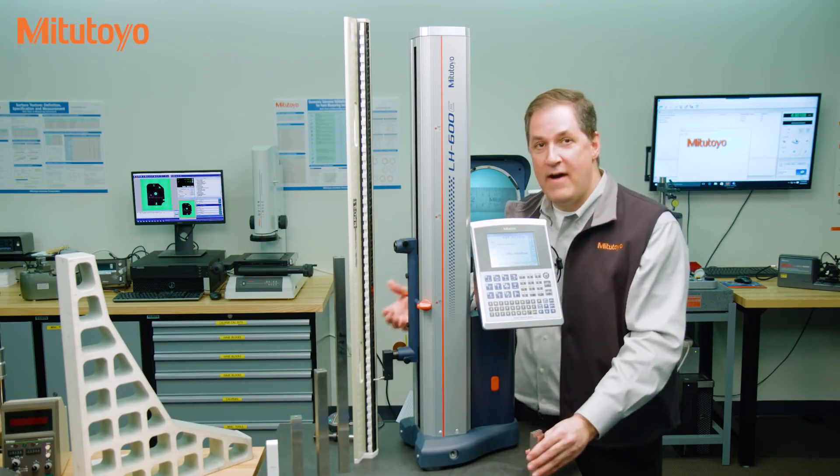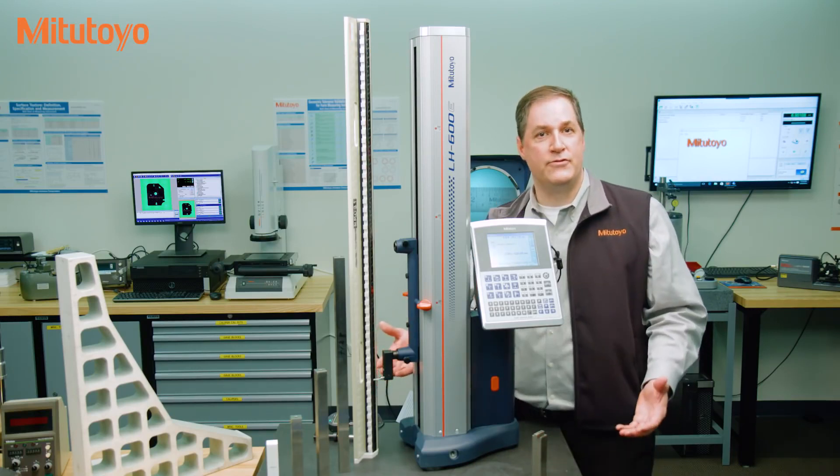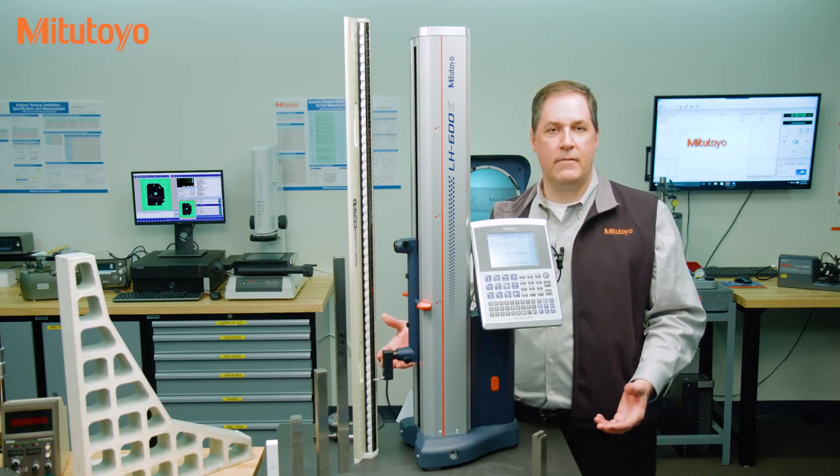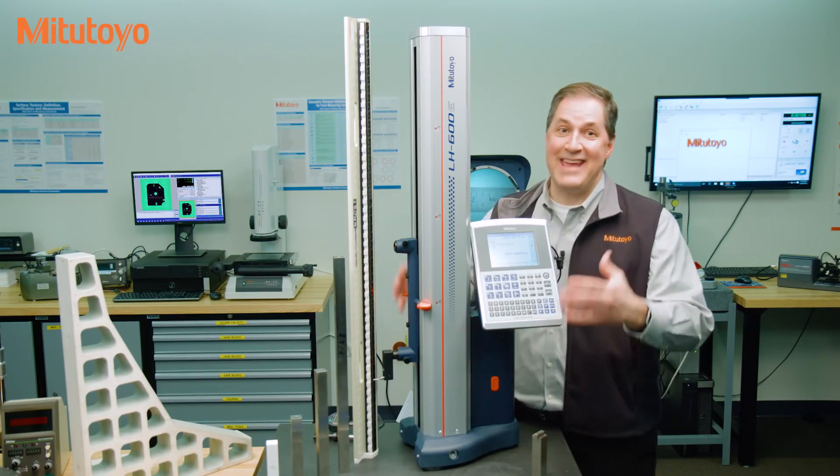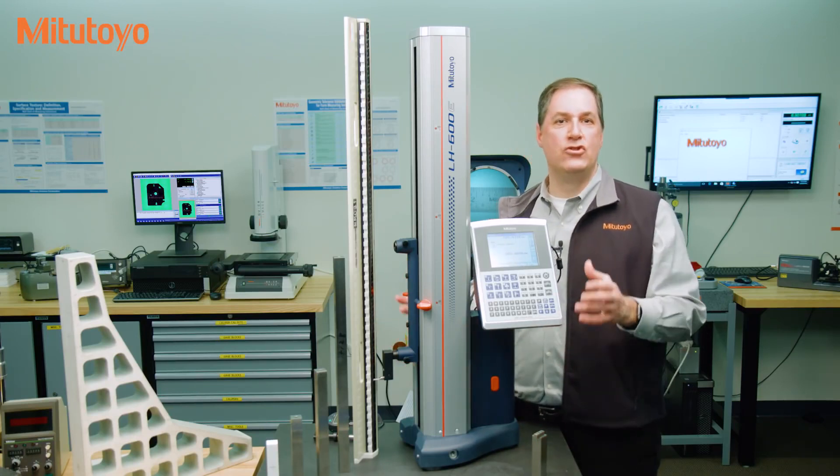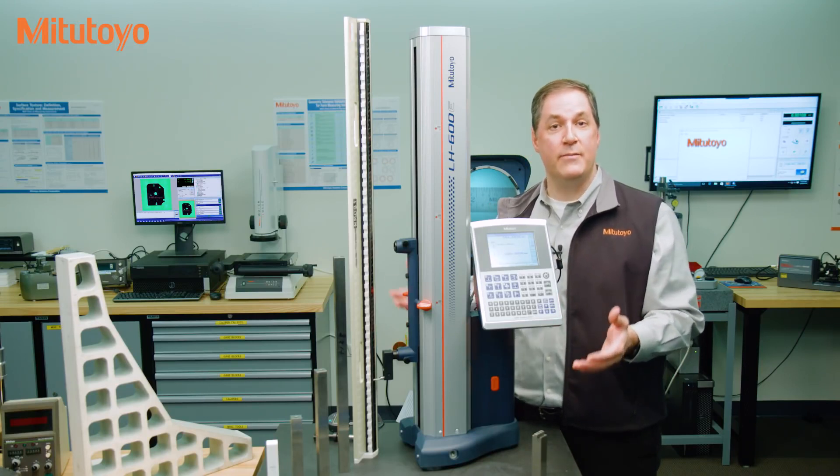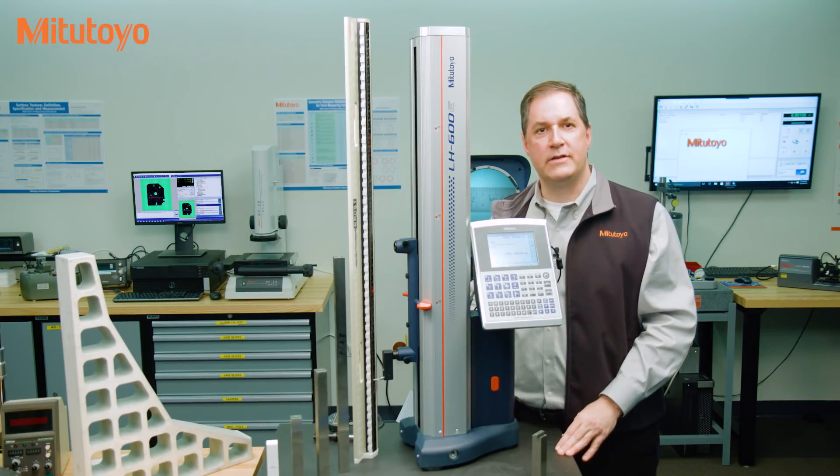So these calibrations need to be done correctly, as they are often tweaking some temporary adjustment to the measuring equipment. If I'm off 5 microns when calibrating the probe diameter, all my measurements will be off 5 microns. It's also important to recognize that doing this probe calibration is not calibrating the entire instrument. Measuring equipment that has these user calibrations still need to be calibrated, as in the first three types of calibrations we discussed earlier.